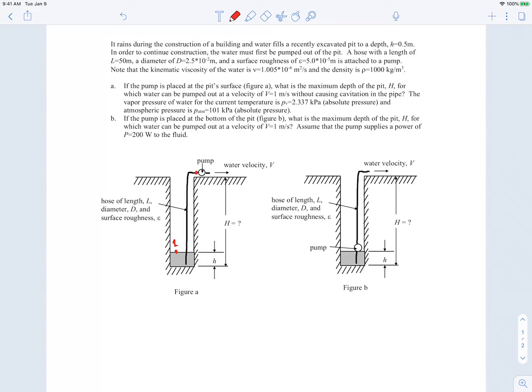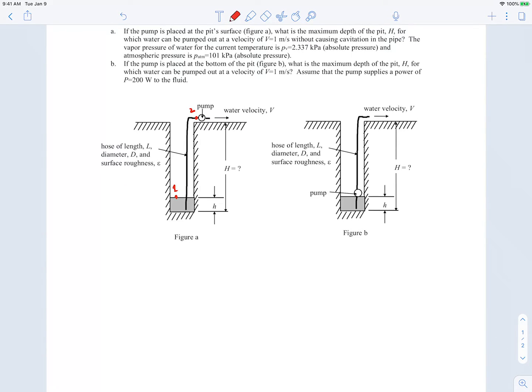For Part A, we apply the extended Bernoulli equation from point 1 (the free surface) to point 2 (just before the pump). Pressure starts at atmospheric at point 1, then decreases due to viscous major losses and increasing elevation. The lowest pressure will be right before the pump, since the pump then increases pressure. We want to ensure that point 2 does not reach the vapor pressure.